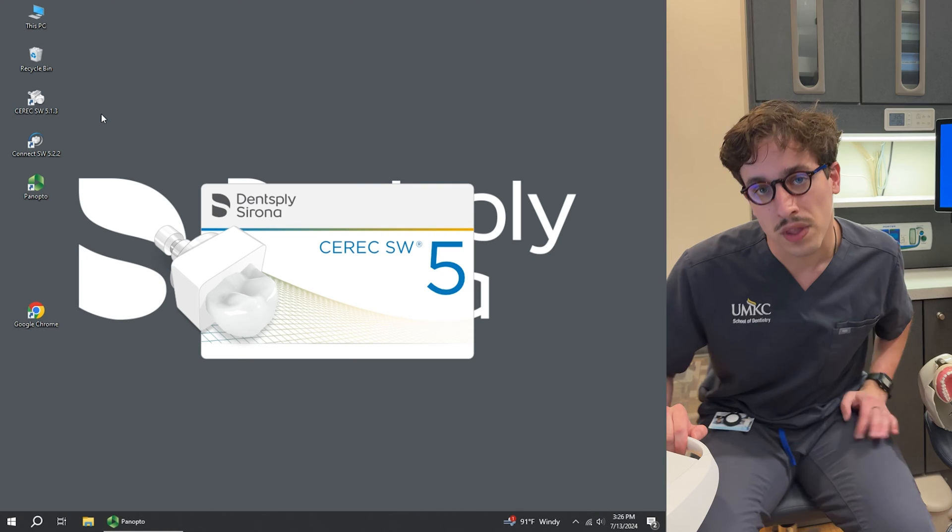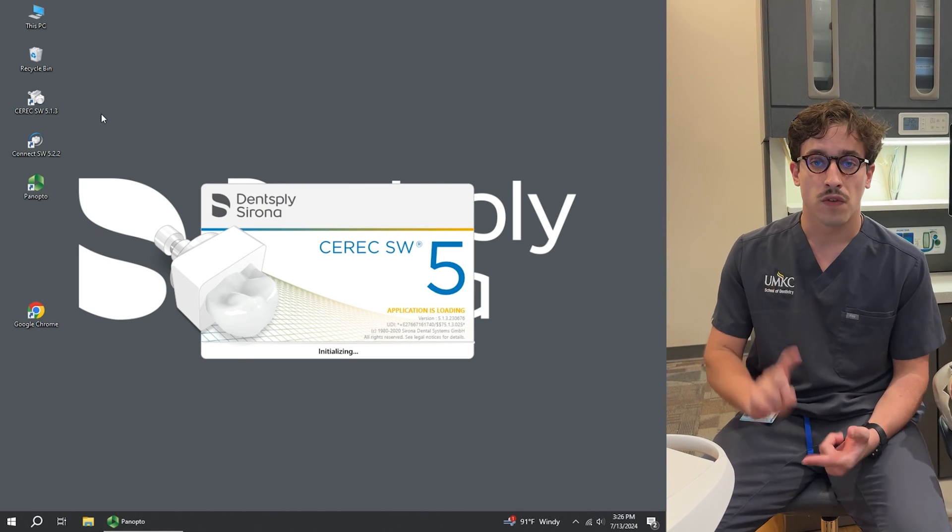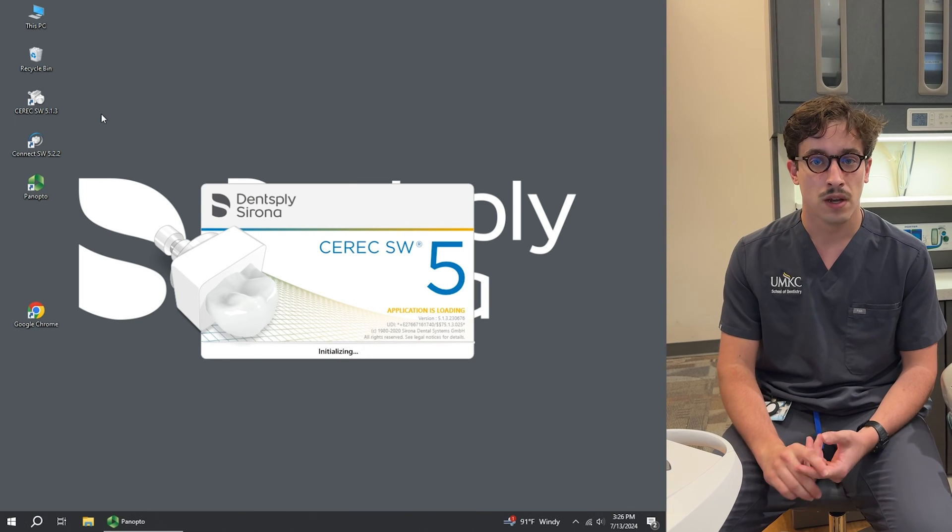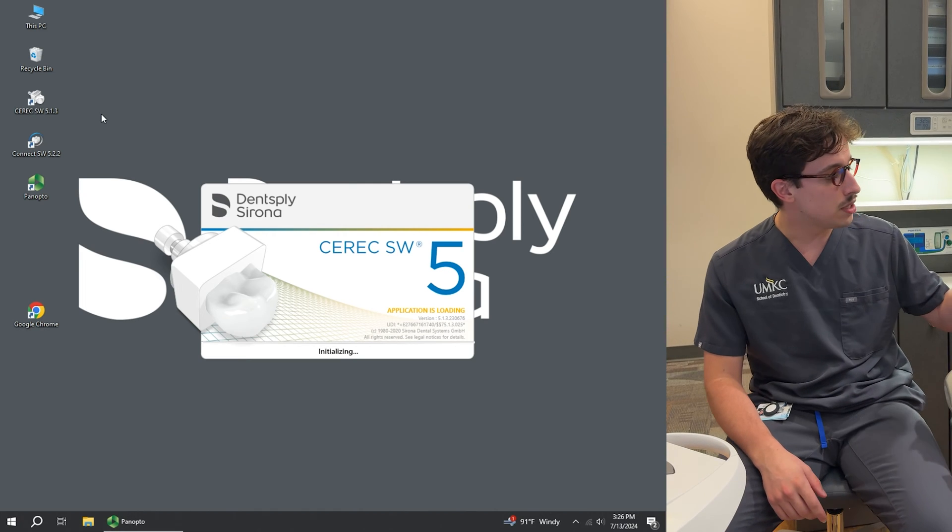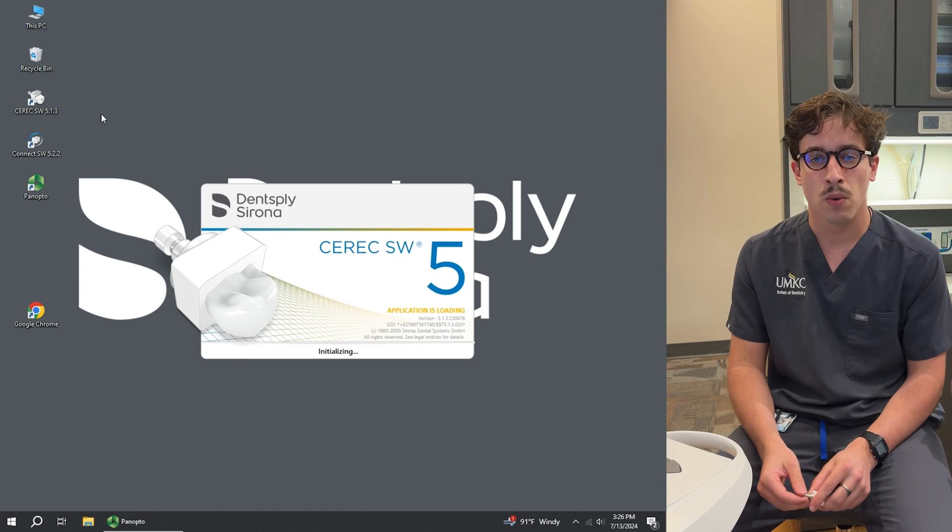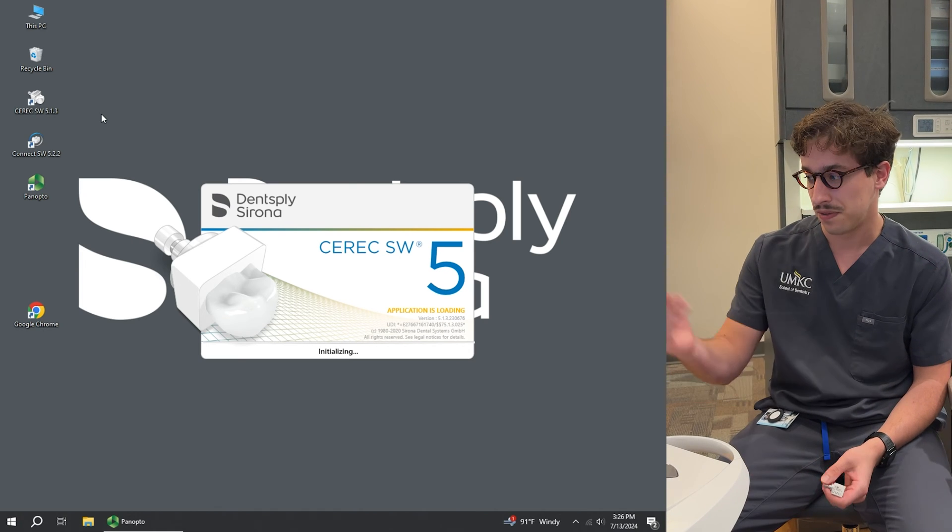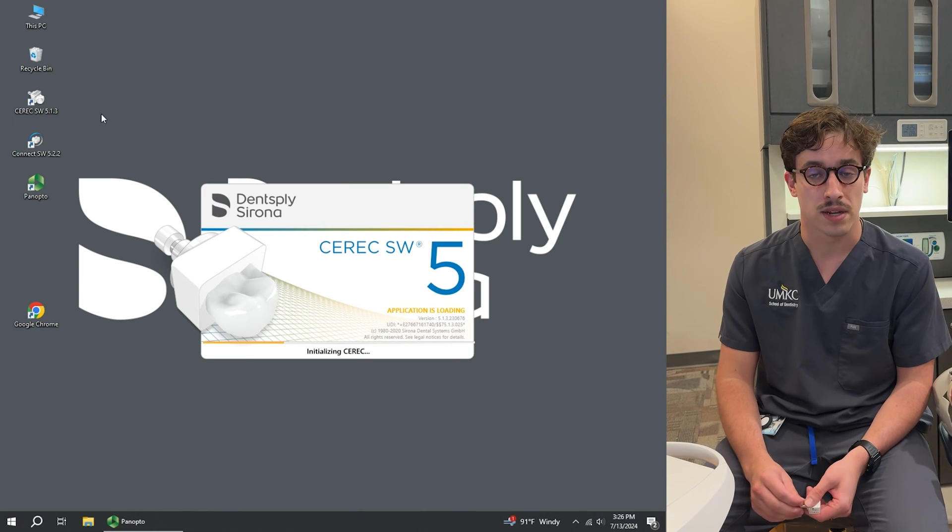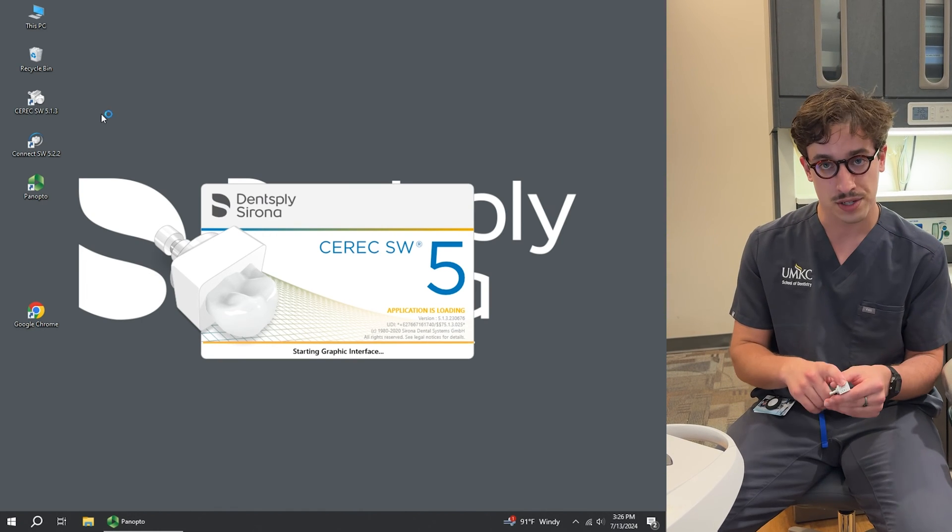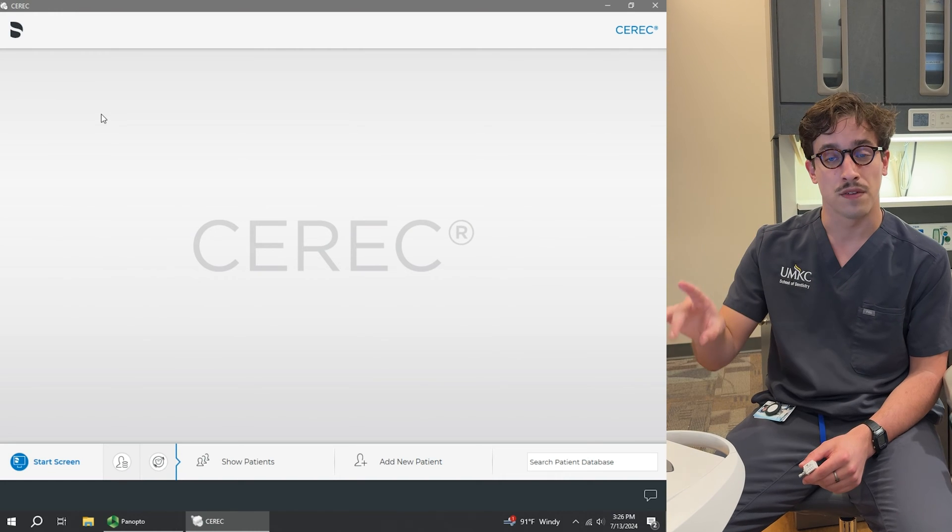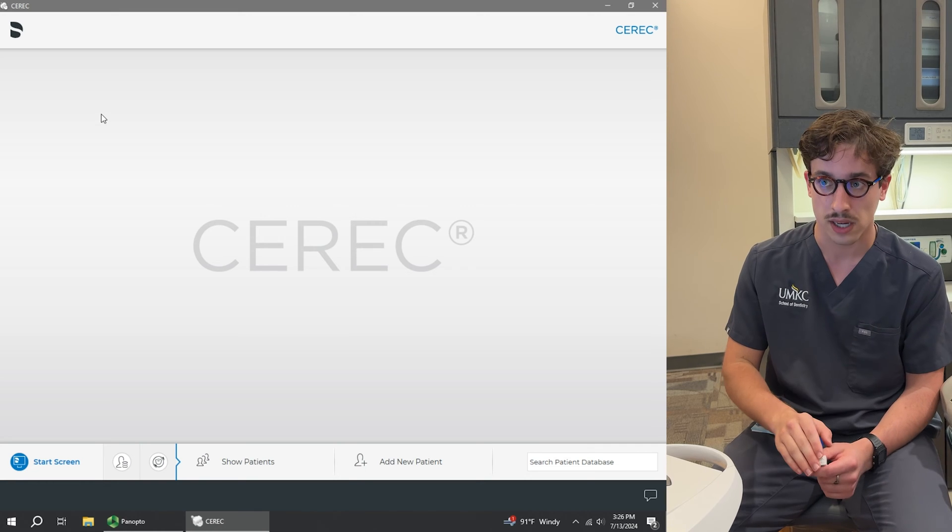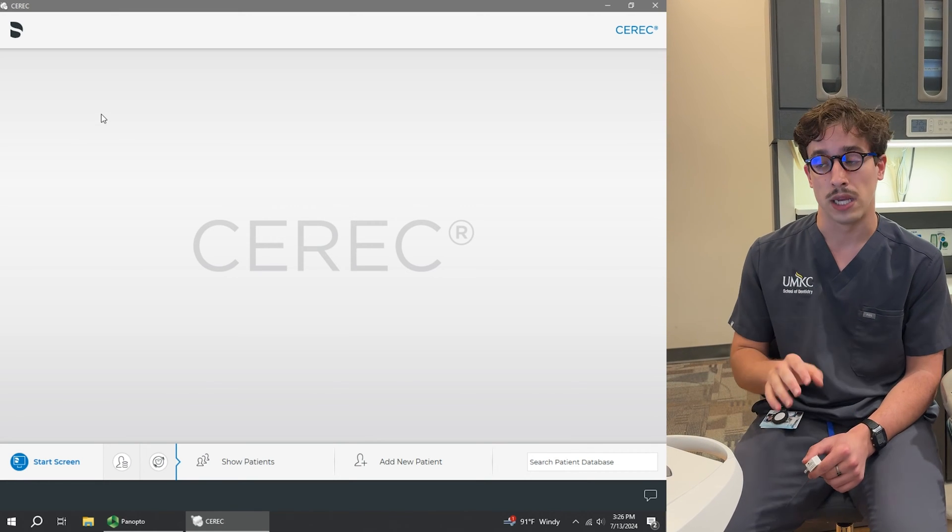Now, the very important thing is that we have to make sure that we're selecting a few things correctly from the beginning. First off, we need to make sure that we're selecting the correct material. We have a bunch of different materials to choose from here. Today we're going to be using our Chairside Zirconia block and primarily what we're milling here as of now, as of July in 2024, we're milling primarily Emax, so Lithium Disilicate, and then we're also milling Zirconia, but specifically Chairside Zirconia. Now you'll see here in the software that there's a lot of different options for Zirconia, and it's really important that we select the correct one, in this case Chairside Zirconia. Otherwise it will not mill properly and we'll have a lot of issues to begin with.